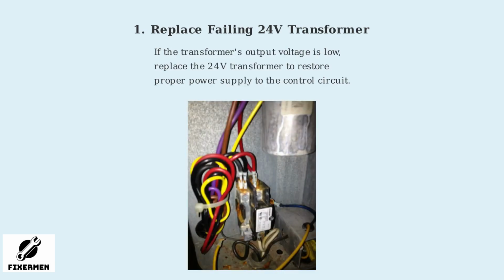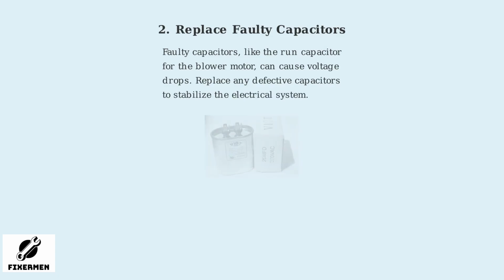The first common fix for error code 115 is replacing a failing 24 volts transformer. If the transformer's output voltage is low, it can cause the low voltage lockout. Replace the transformer to restore proper power supply to the control circuit. The second fix involves replacing faulty capacitors. Components like the run capacitor for the blower motor can fail and cause voltage drops leading to the lockout. Inspect and replace any defective capacitors to stabilize the electrical system.